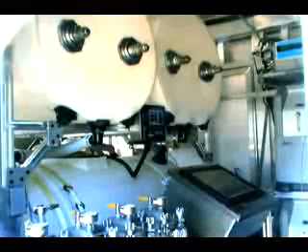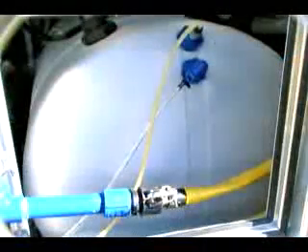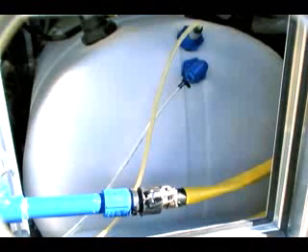The water and ozone are mixed together using a new and novel approach that ensures ideal mass transfer of the ozone to the water. This is a NEOS proprietary and patented process. The ozonated water passes through a clear well that gives a 3-minute contact time with the ozone while it disinfects the water. The next treatment step is ultraviolet. The UV dose is 1000 millijoules per square centimeter, or 1 watt-second per square centimeter of 254 nanometer ultraviolet light. This is hundreds of times the amount required to kill disease-causing pathogens. The NEOS equipment absolutely ensures your drinking water safety.